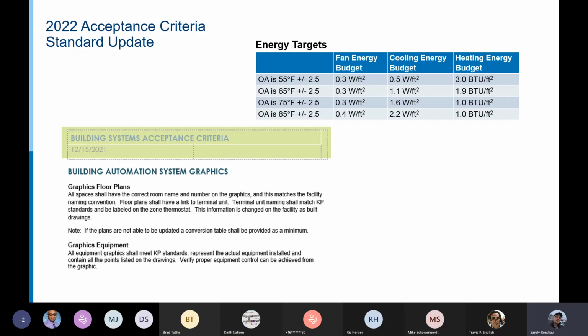All spaces need to have the correct room name and number on the graphics, matching the facility naming convention. Floor plans shall have a link to the terminal unit, terminal unit naming shall match the KP standards and be labeled on the zone thermostat. This information is changed on the facility as-built drawings, and if the plans are not able to be updated, a conversion table should be provided.